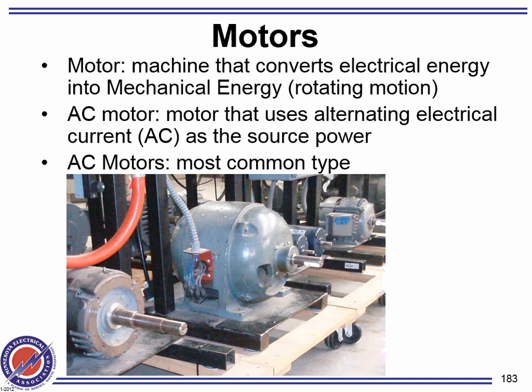Okay, now motors. Coils, and inside them a chunk of steel. Once you couple this shaft and add to it a machine, a fan or something, or you've got yourself a load on this motor, a fan, a conveyor, whatever. You plug in from the shaft. So the shaft is the point of coupling between your mechanical loads and electrical loads. The power comes from here, gentlemen, and gets converted inside this machine from electrical power into mechanical power, and the mechanical power comes in the form of rotation.